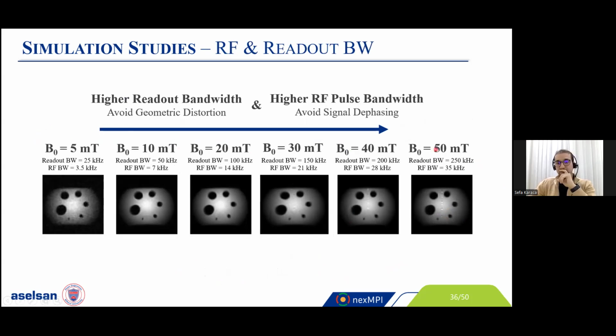As you can see here, as we increase the B0 field, if we also increase our readout bandwidth, we can avoid the geometric distortion artifact. If we increase the RF pulse bandwidth, we can avoid the signal dephasing artifact. By doing so, we can maintain the same image quality even in the case of 50 millitesla.